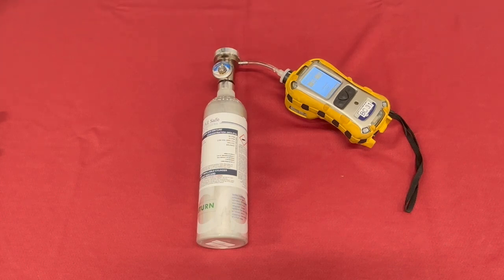Okay, we've got just a couple minutes here. Let's talk about calibration and bump testing. Calibration is actually adjusting the sensors to the known calibration gas. You can think of this very similar to putting a known weight on a scale and adjusting the scale to that known weight. We're actually telling the meter to move the sensor to that known amount of gas. That's one reason that this takes so long. It takes time for the sensor to get to where it's going to level out and then make the adjustments.